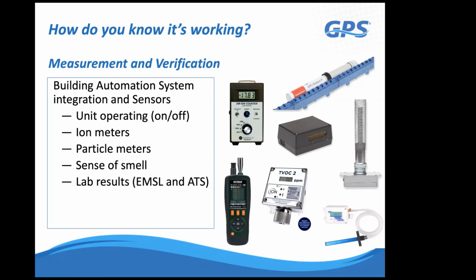Now, if you want to know the actual ion output, not just what voltage we're sending to the bar, which is what we're measuring with the microprocessor, then you need a handheld meter, which measures your ions. You could also use a space mount meter if you want a permanent solution, or a duct mount ion meter. And both of these meters provide a 0 to 10 volt output back to your building automation system.